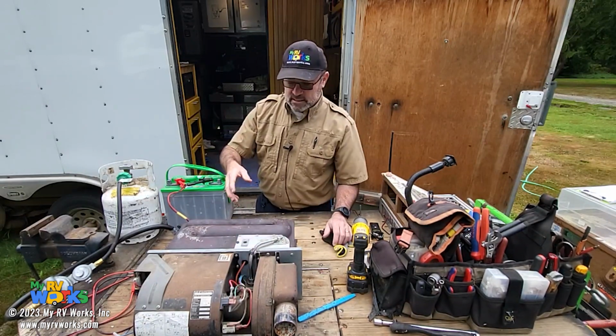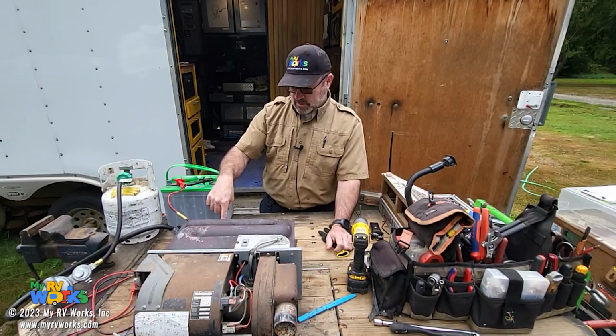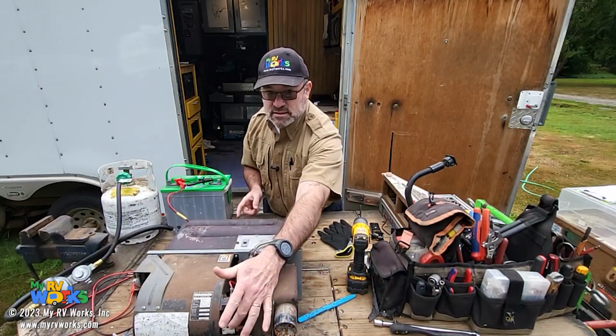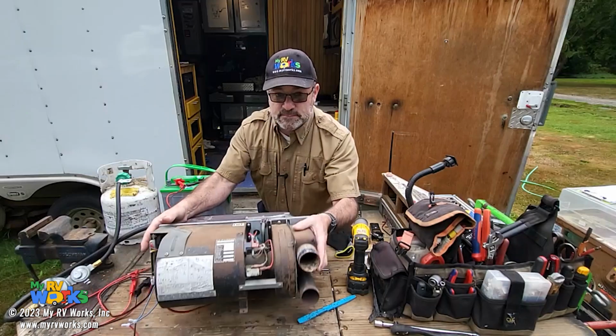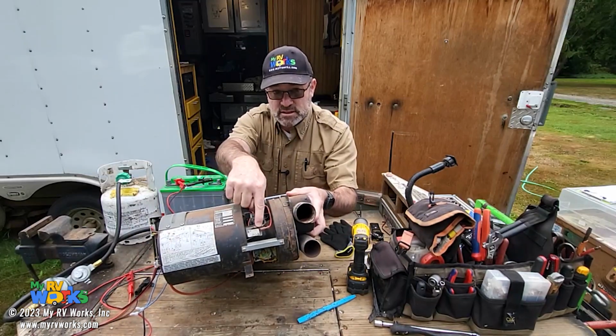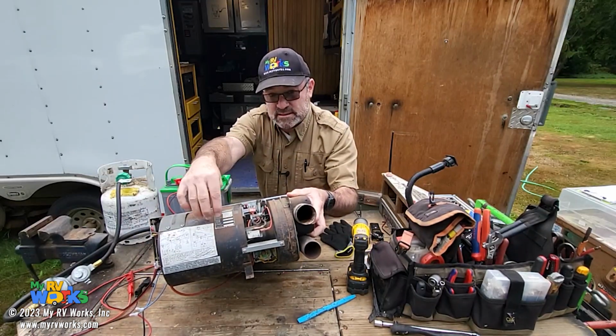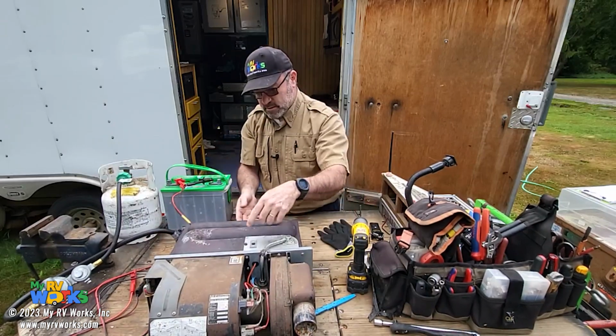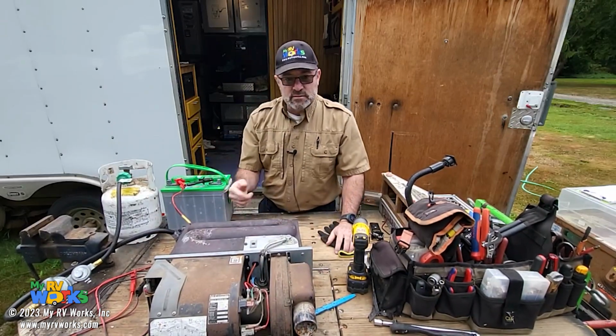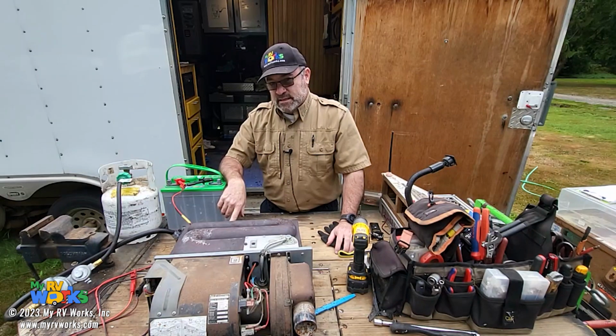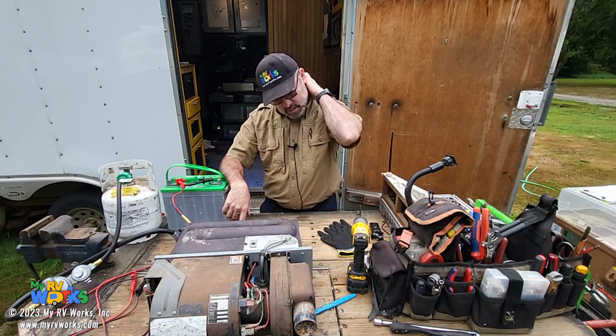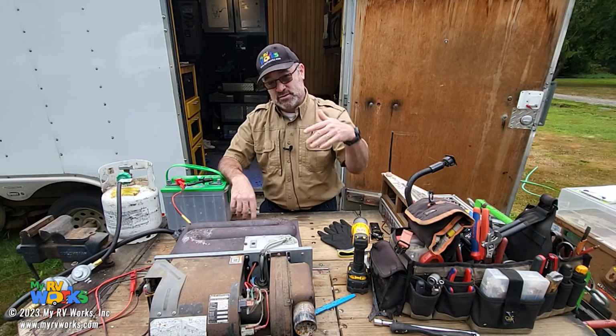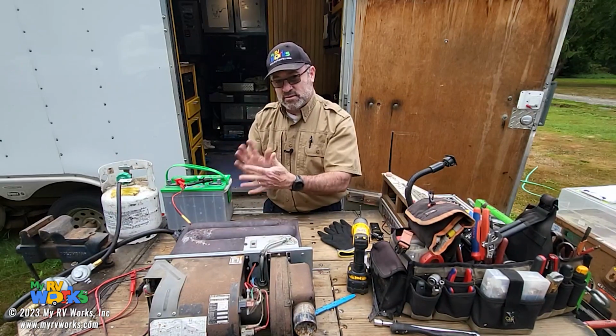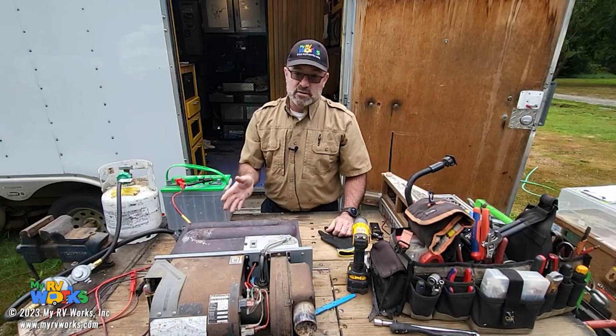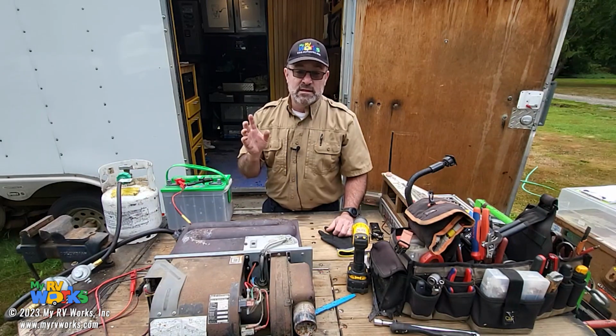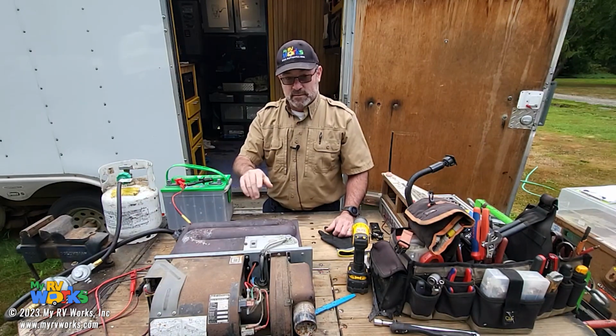The other thing I said is it could be a faulty sail switch, or a faulty high temperature switch, and I'm pointing to them. This is a sail switch on this furnace here. On this SF30F, the sail switch is right here. Some of them are inside this cover. And on the back side of this one, we'll spin it around so you can see it, is the high temperature switch. You've got the blue dot, green dot, orange dot, and all that has to do with the BTUs of the furnace and the temperature where it trips off. Make sure that when you replace that, you replace it with the correct color dot thermostat, okay?